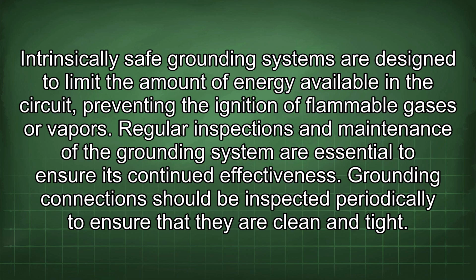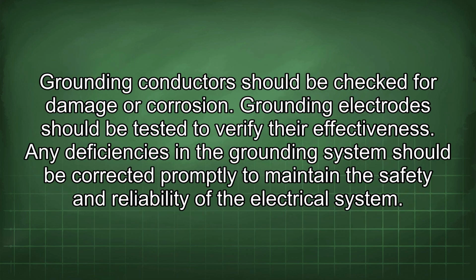Grounding connections should be inspected periodically to ensure that they are clean and tight. Grounding conductors should be checked for damage or corrosion. Grounding electrodes should be tested to verify their effectiveness. Any deficiencies in the grounding system should be corrected promptly to maintain the safety and reliability of the electrical system.